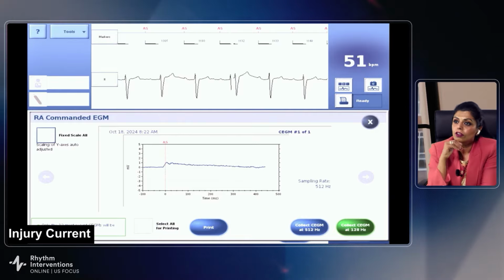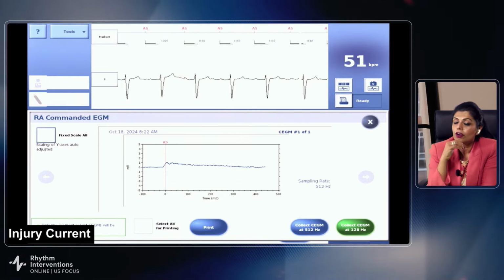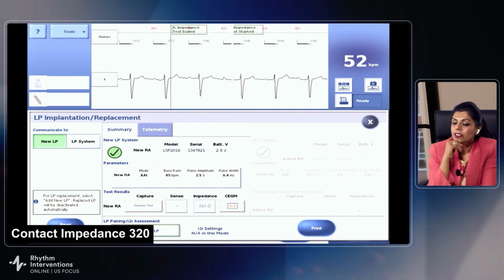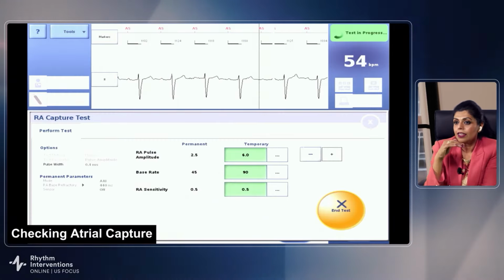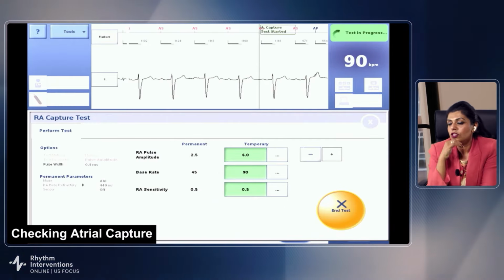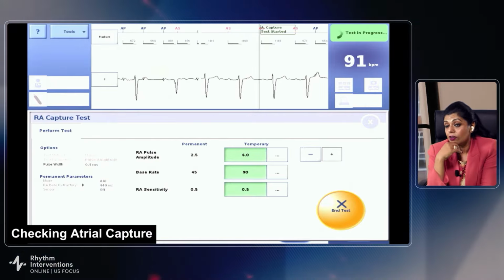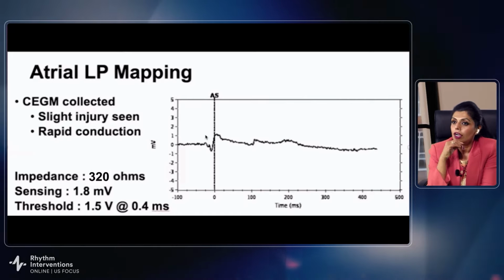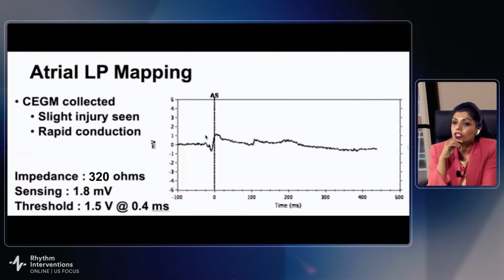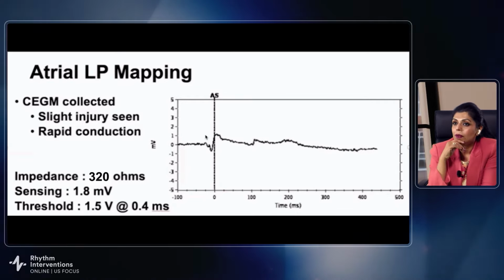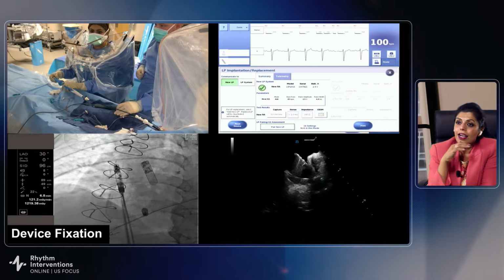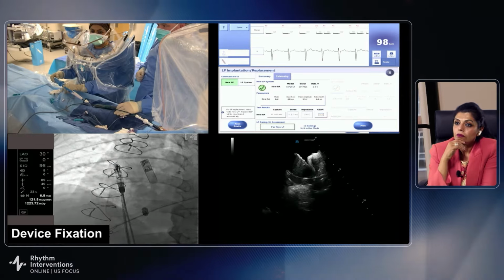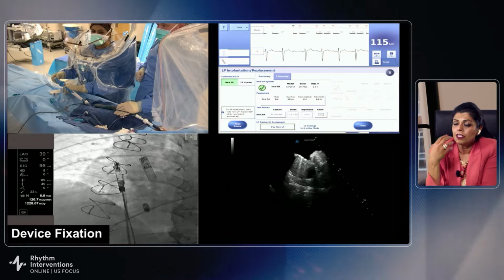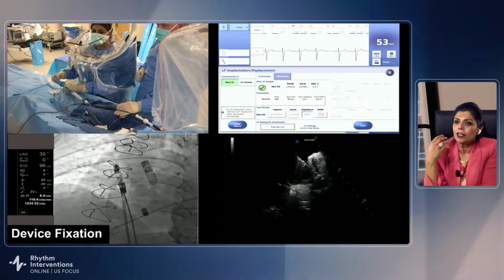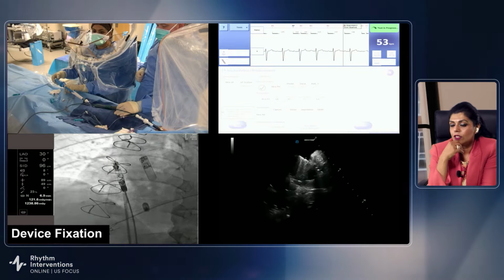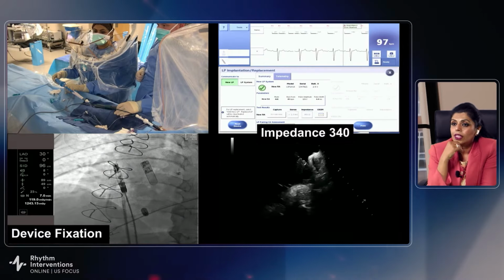and I'm looking at the appendage in its longitudinal fashion. We're looking for an injury current where we're off the baseline. You're again looking for a slight impedance rise. You're not going to see high impedances like in the right ventricle. Somewhere in the low 300s, upper 200s range is where I usually see impedances for the atrial device. And again, as we're fixating, we are looking for that impedance rise, but usually about 20 to 40 ohm rise is what I have seen with the atrial device.